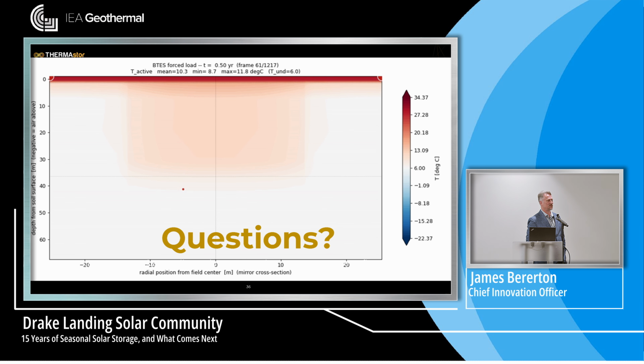And what was the cost to decommission the project? Yeah, it was pretty significant. They had to take all the solar collectors off the roof and re-roof all the garages, because they didn't maintain the O-rings, they leaked glycol on various garage roofs. They could have paid to replace the O-rings instead—that would have been cheaper. Even then, if you'd replaced it, you'd have had a protected roof underneath. It should have been okay if it hadn't leaked.